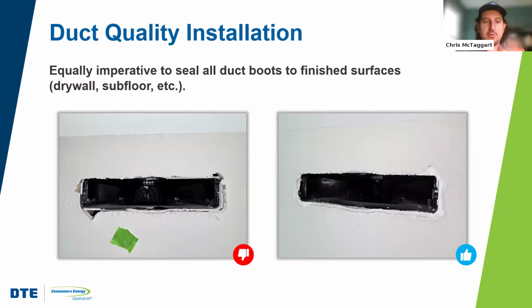Why? Because otherwise, when we have that grill face over the boot, then air is slamming against that grill with significant velocity, and some of it's going to end up bouncing back and going back into the wall or the ceiling cavity. And especially if you have any ducts that are outside of conditioned space, that's going to exacerbate that issue and cause there to be leakage to outside. So you can see a savvy rater probably ran their test and realized they were not passing, chose to pull off the register grill face and saw that there were significant gaps around a good portion of those boot connections.